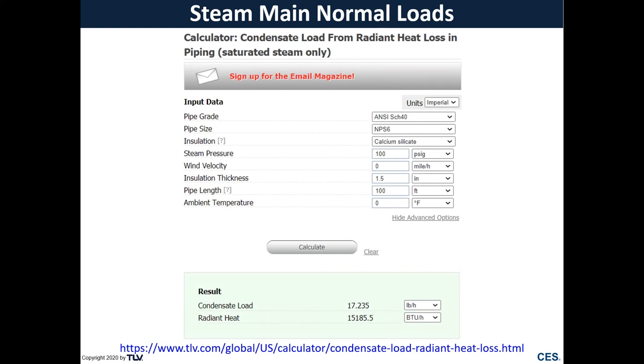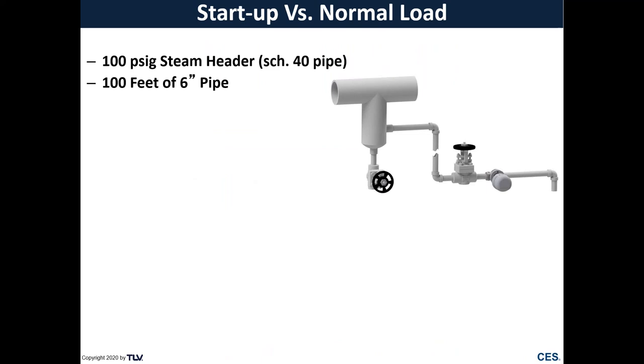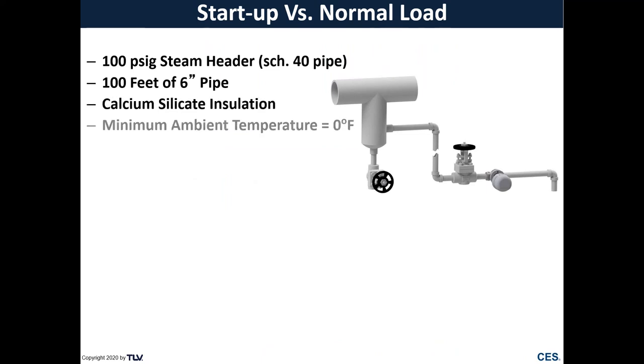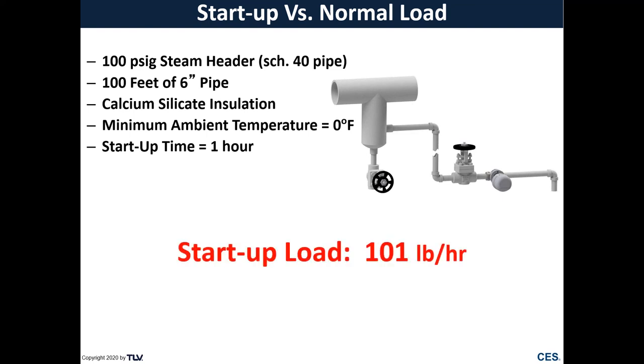If we go through an example of this, looking at a typical steam main, we'll say 100 PSI steam header and 100 feet of 6-inch pipe with typical insulation in a very low ambient condition. If we consider a 1 hour startup time, our startup load for this type of application is only going to be about 101 pounds an hour. So not a whole lot of condensate. Most 1/2 inch or 3/4 inch steam traps are going to be able to handle that amount of load. And if we look at our normal load, it's even lower at only about 17 pounds an hour.